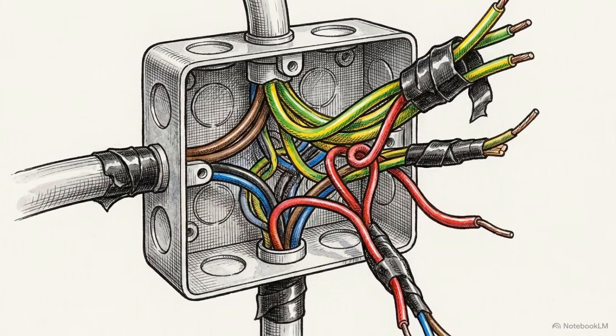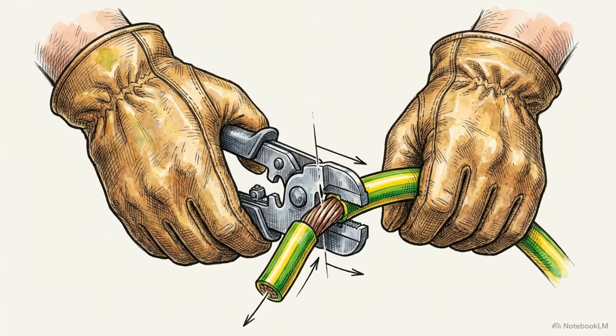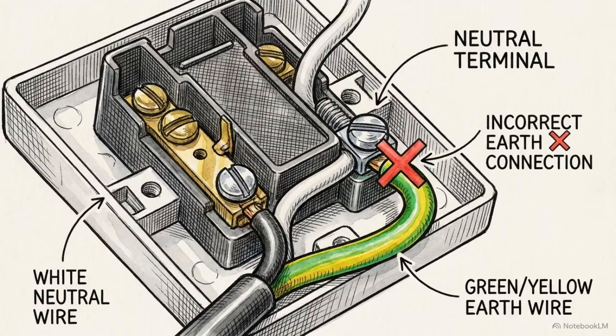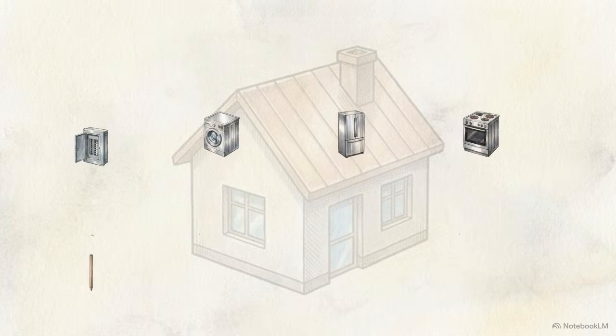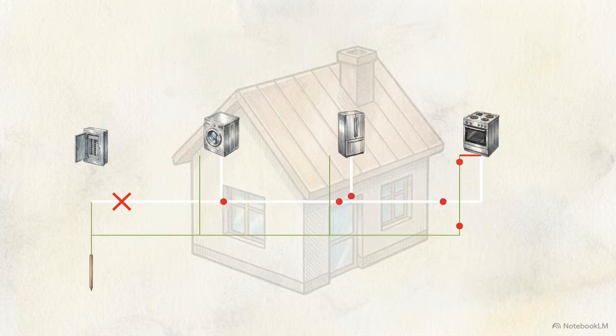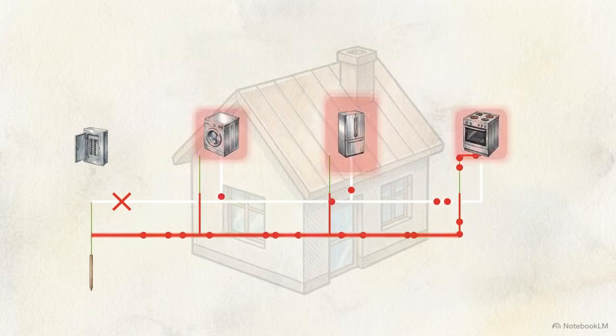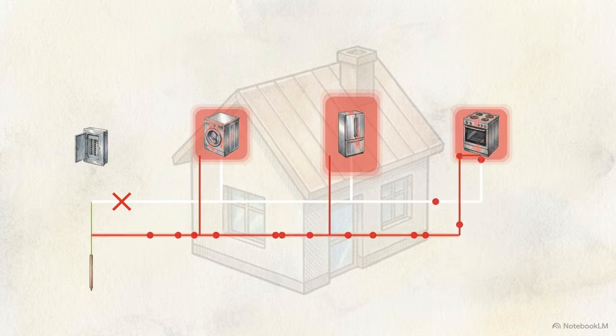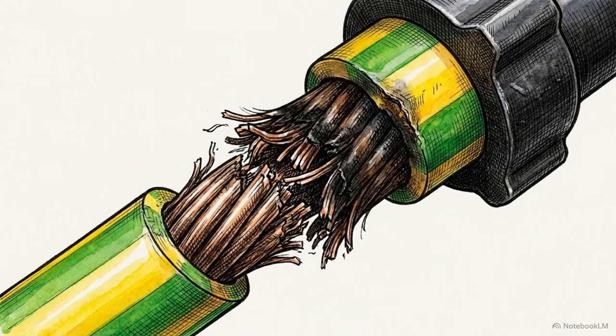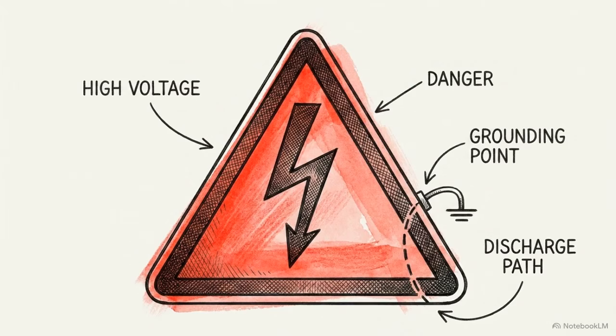Bringing this back down to the residential scale reveals how confusing these precise engineering terms leads to illegal, deadly wiring practices. A common shortcut occurs when an installer decides to use the safety earth wire as the neutral return path to power a device. This forces everyday operating current through the green earthing wire, but that protective path is physically thinner and has a naturally higher resistance. This creates a continuous voltage drop, actively energizing the outer metal casings of the washing machine, refrigerator, and oven. By forcing a protective path to act as a return path, a system explicitly built to save lives is transformed into an active shock hazard.